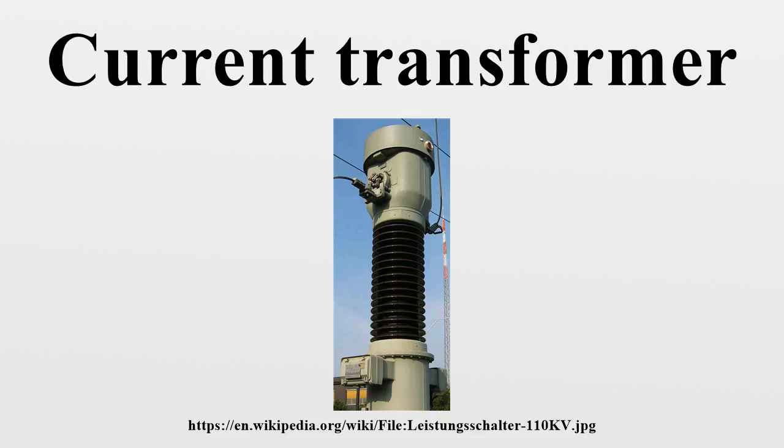A CT with a rating of 2.5 L400 specifies an output from its secondary winding of 20 times its rated secondary current and 400 V at its output. Accuracy will be within 2.5%.